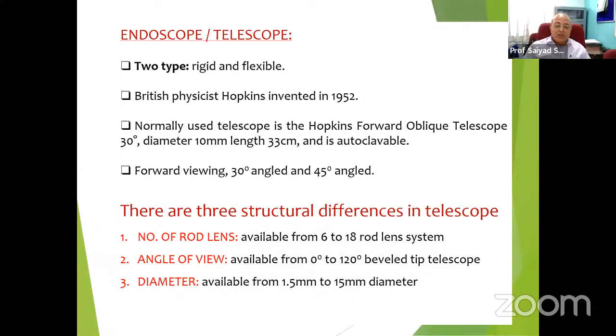Now, the most commonly used telescopes in terms of lens, angle, and diameter: thin lens and Hopkins rod lens. Hopkins rod lens is better than the thin lens. Thin lens is cheaper. Hopkins lens gives a very good quality of picture, like HD, Super HD, 4K, and so on. But picture quality will get better day by day as advancements come. The angle of view is 30 degree: a 30 degree telescope provides a 152 degree viewing angle. If we use a 0 degree telescope, it provides 76 degree.